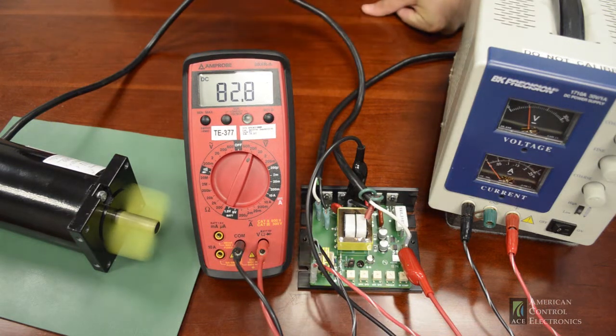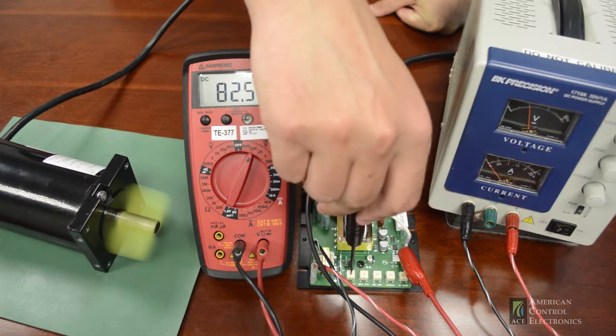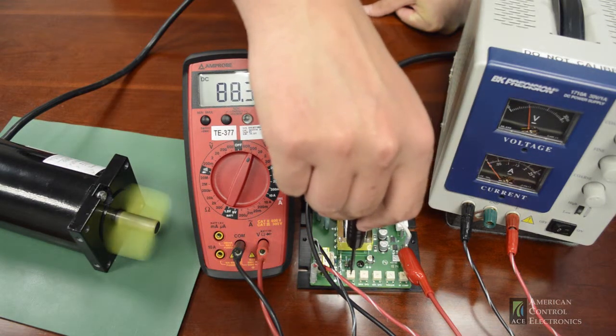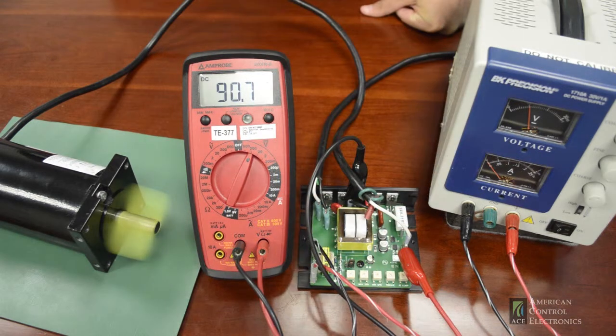We want the drive to output 90 volts. We'll turn the trim pot clockwise until we reach 90 volts and tighten it up like so.